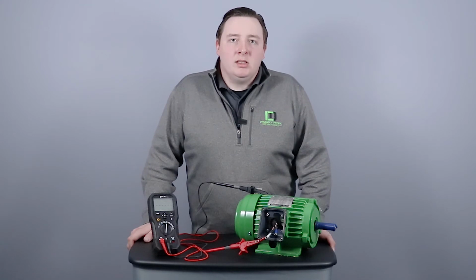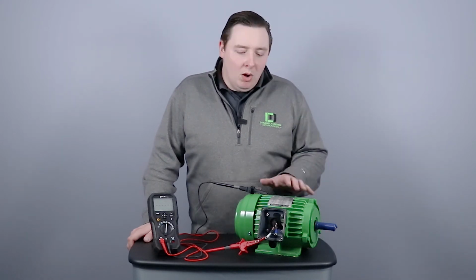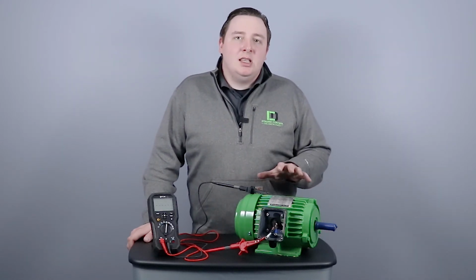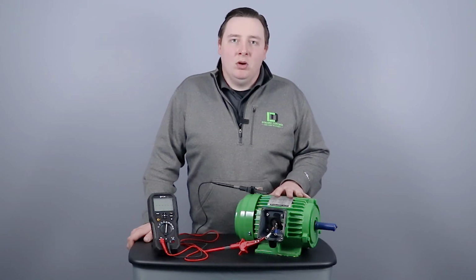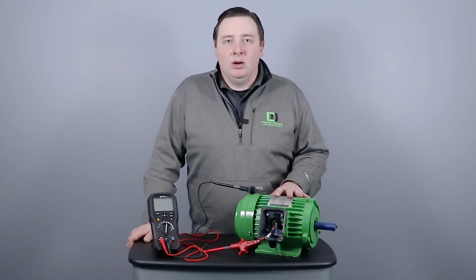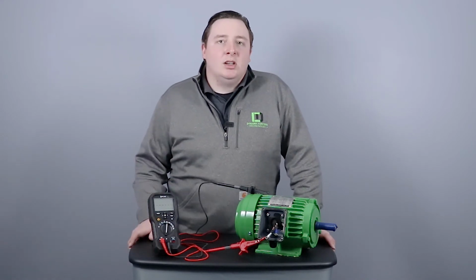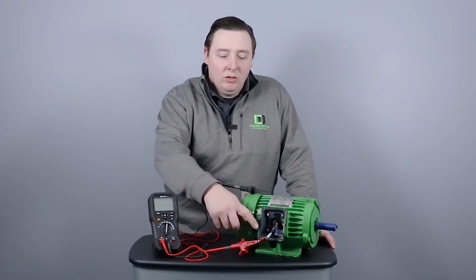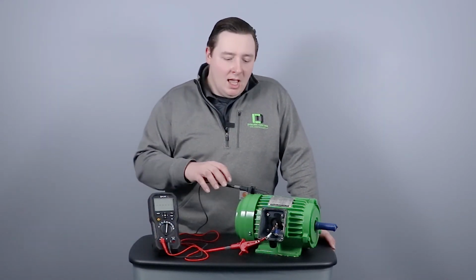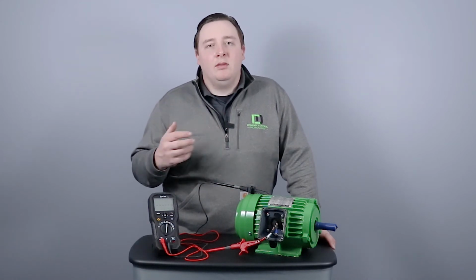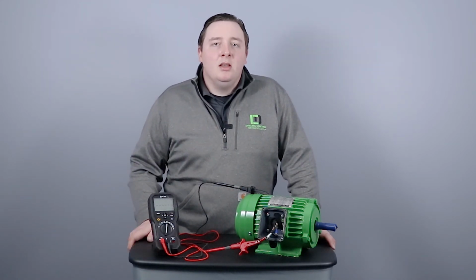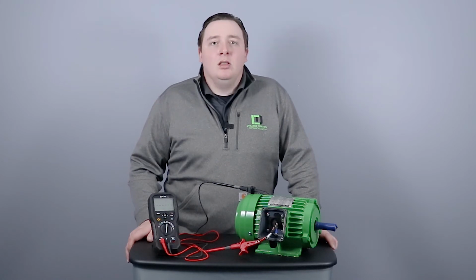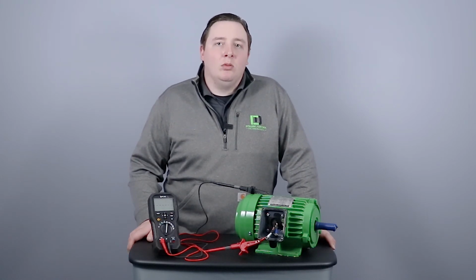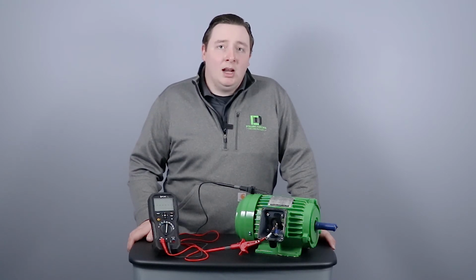One of the most difficult is being able to identify motor insulation issues. Because the insulation is on the windings inside the motor, it's not apparent from the exterior of the motor. Utilizing an insulation tester, we are able to source voltage through the individual windings and be able to reference ground to identify if there's any direct shorts in the motor, therefore identifying that electrically the motor is okay. We are then able to remove that from being one of the causes of the issue or being able to identify that that is in fact the problem.